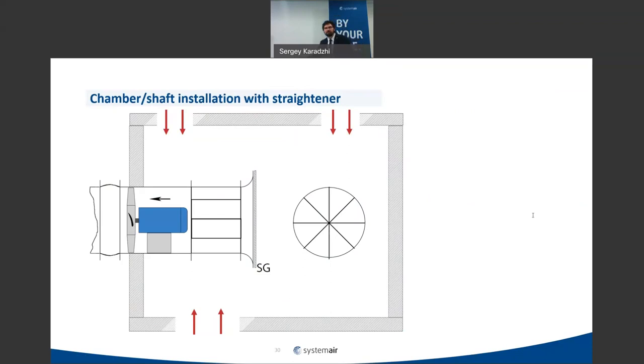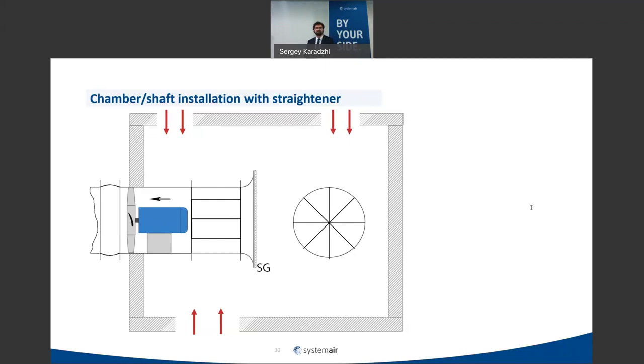A question was asked about the impact of airflow direction from impeller to motor. The answer is that it depends on the fan design. In some cases there is small influence, in other cases not. For example, if the motor has its own cooling impeller and the main fan flow goes in the opposite direction, it is sometimes better to use the direction from impeller to motor.